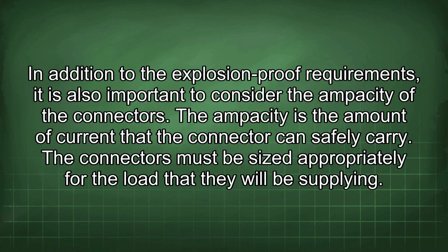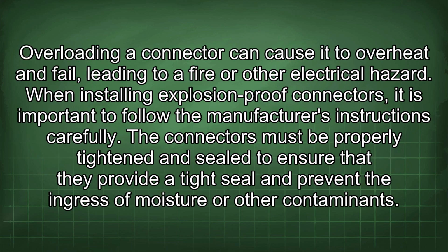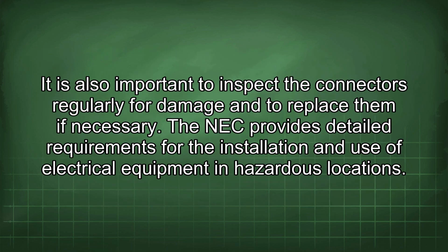In addition to the explosion-proof requirements, it is also important to consider the ampacity of the connectors. The ampacity is the amount of current that the connector can safely carry. The connectors must be sized appropriately for the load that they will be supplying. Overloading a connector can cause it to overheat and fail, leading to a fire or other electrical hazard. When installing explosion-proof connectors, it is important to follow the manufacturer's instructions carefully. The connectors must be properly tightened and sealed to ensure that they provide a tight seal and prevent the ingress of moisture or other contaminants. It is also important to inspect the connectors regularly for damage and to replace them if necessary.